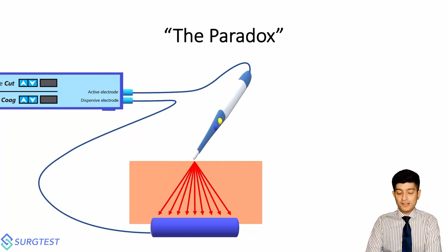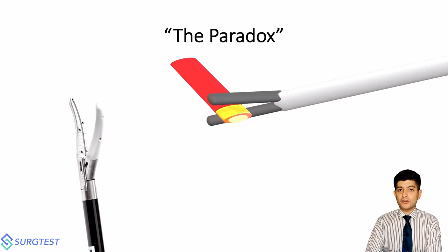The reason for that is very straightforward. It's that current density has changed as a result of the amount of tissue which is being grasped. When you land up using a cutting current on a monopolar device, you have an extremely high current density at the tip of the device, which lands up giving you the cutting effect. But when you're using the same form of cutting current on a bipolar device, you're doing it across a tissue bridge. And because there is a tissue bridge, the current is spread across that entire area that lands up forming a good intimal seal, but you cannot achieve vaporization because of the sheer amount of tissue that is being grasped.